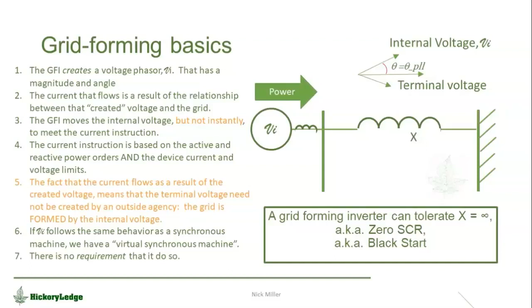It's very similar to a synchronous machine if we ask it to do that. The internal voltage, the VI of a synchronous machine, is governed by a whole bunch of physics related to the iron, copper, and excitation of the synchronous machine. But we can make VI do anything we want, and I'll harp on that for the next couple slides. It fundamentally alters the behavior so that the current injected is a consequence of the control action, not the fundamental control action itself. Big difference.